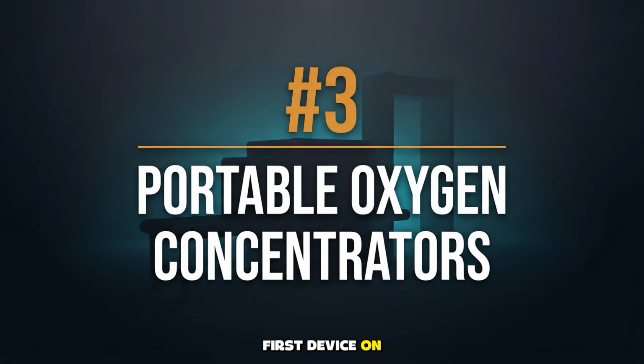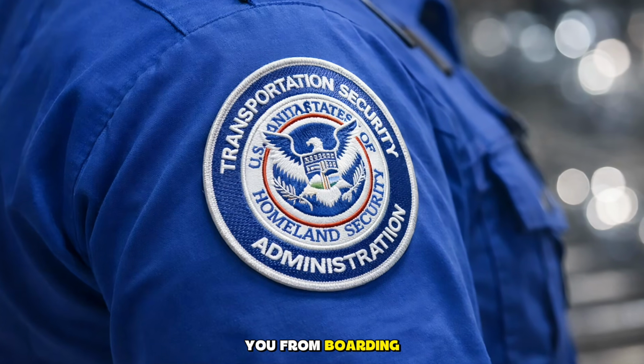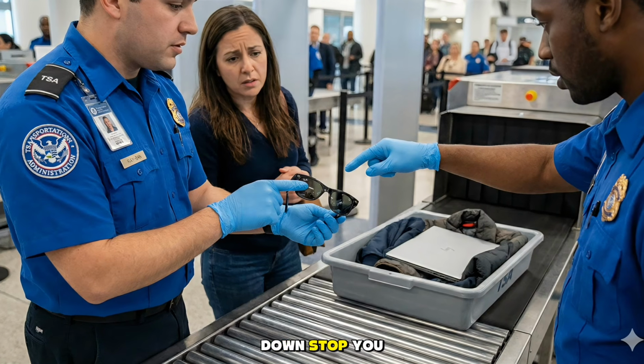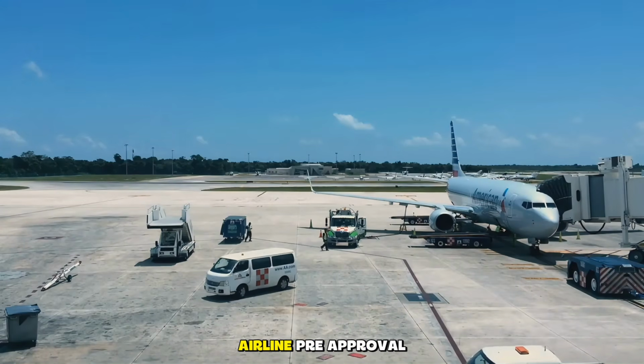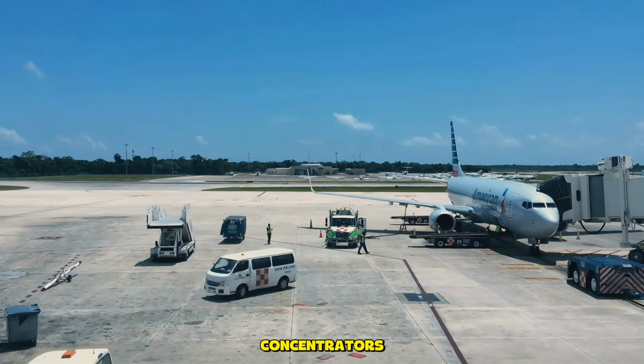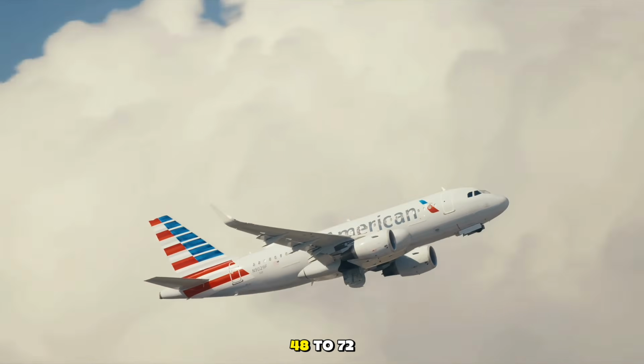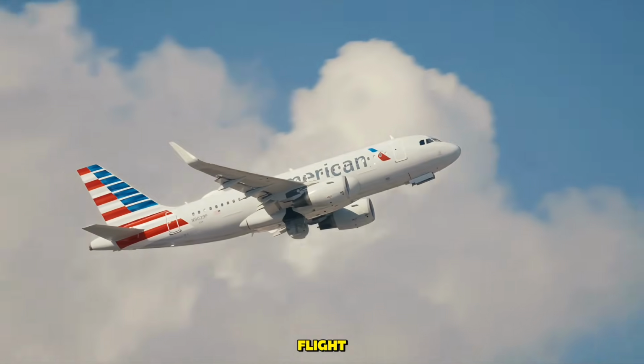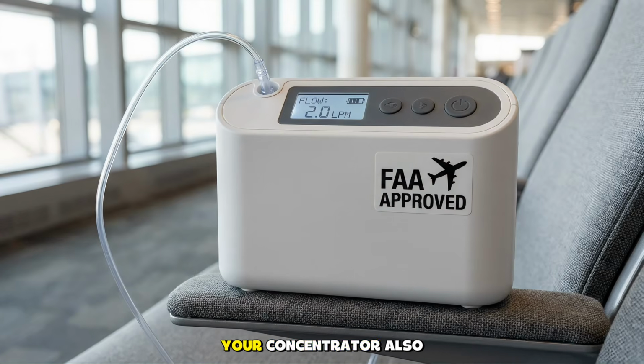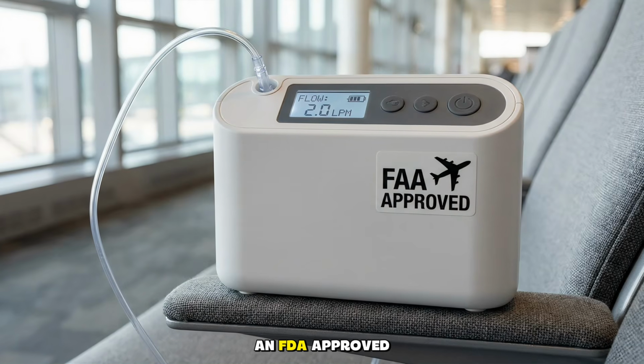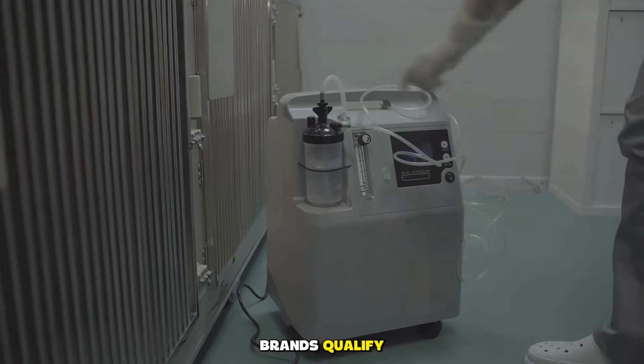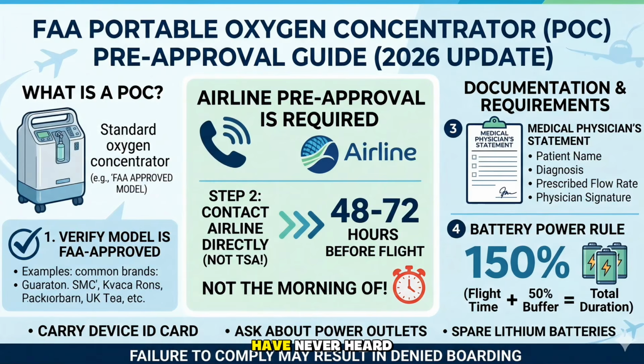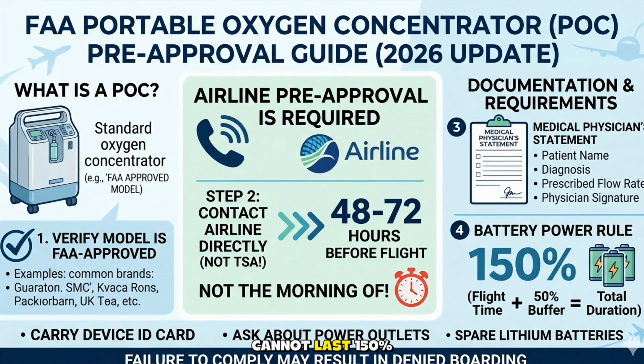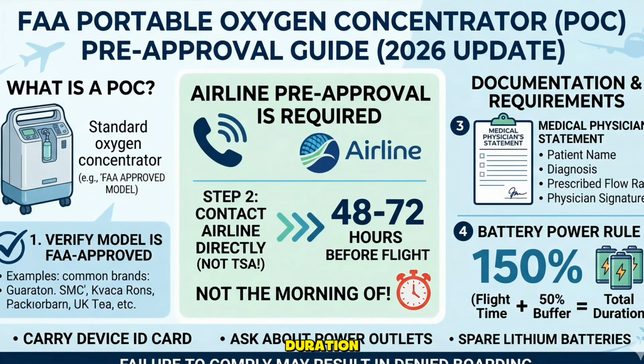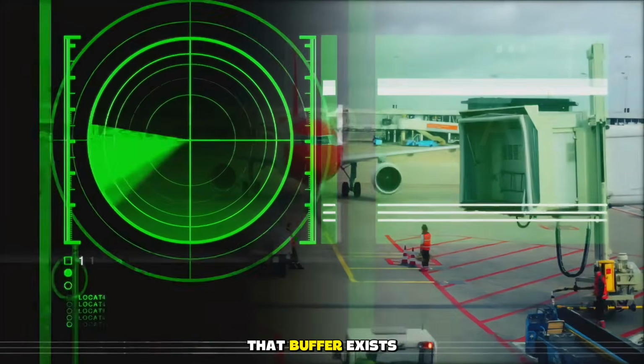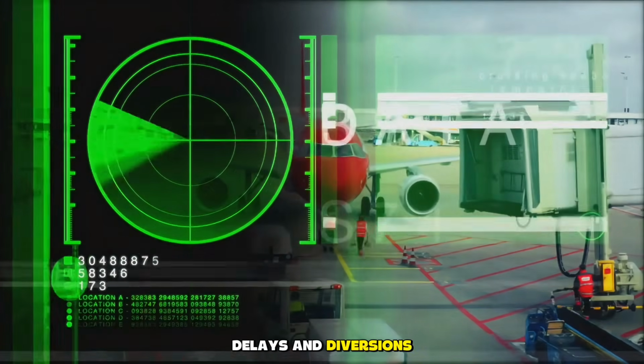This is the first device on this list where the rule change could stop you from boarding entirely, not slow you down, stop you completely. The FAA requires airline pre-approval for portable oxygen concentrators, and that approval needs to happen 48 to 72 hours before your flight. Not the morning of. Your concentrator also needs to be an FAA-approved model, and not all brands qualify. Here is the rule most people have never heard. If your battery cannot last 150% of the flight duration, you may be denied boarding. That buffer exists because of potential delays and diversions.